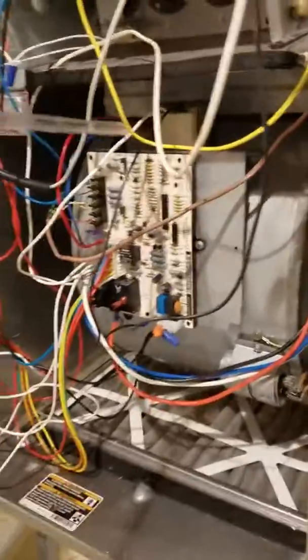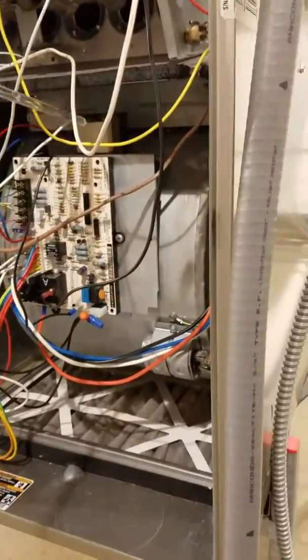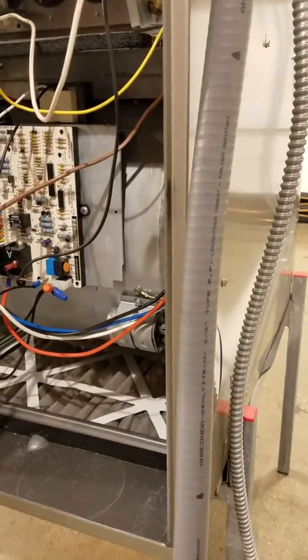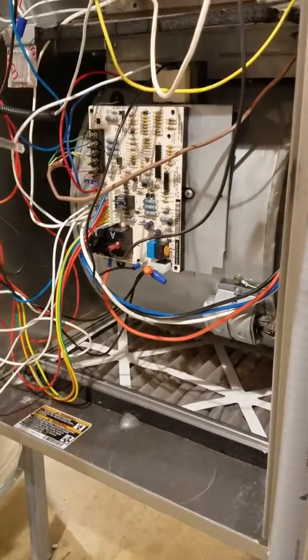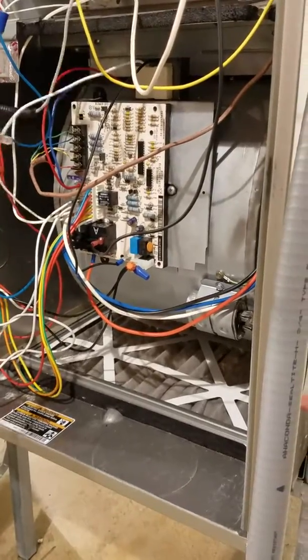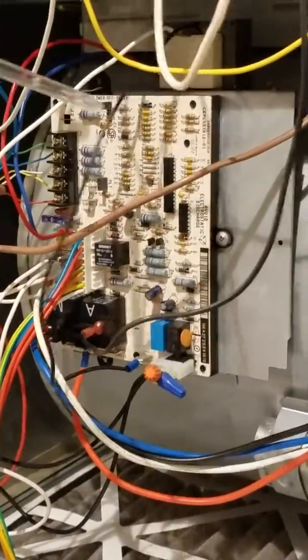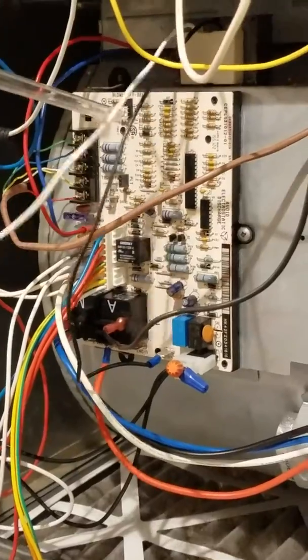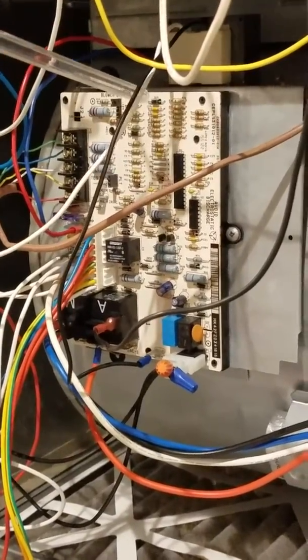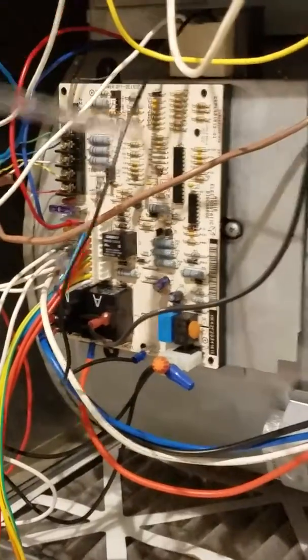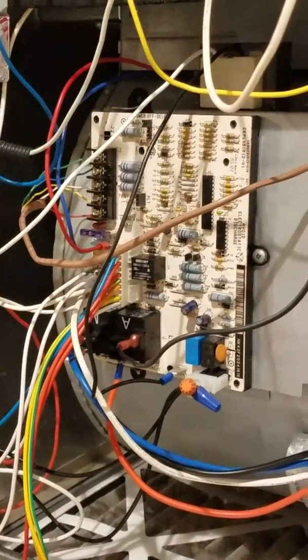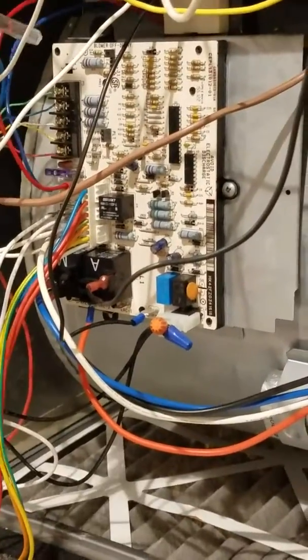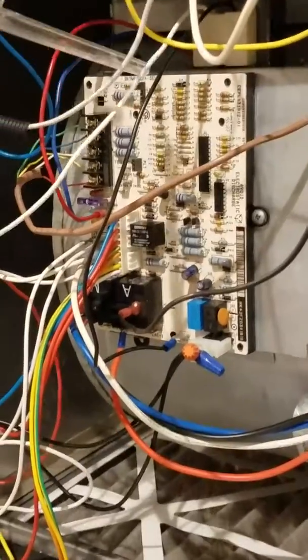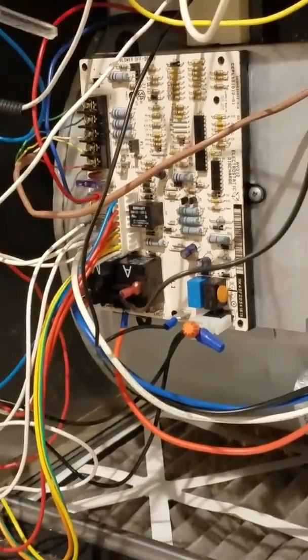Then I come down, and here's my circuit board. Well, before that, I have my transformer. What it does is a step-down transformer, and again, as you can tell, this is common, white, the mistake I made yesterday. I burnt down my transformer and paid for it from my pocket. And the common black, which is good, so this is inlet, it takes 120. Why? Because this is a gas furnace. So it takes in 120 and it puts out here, let me see, these two wires put out 24 volts.